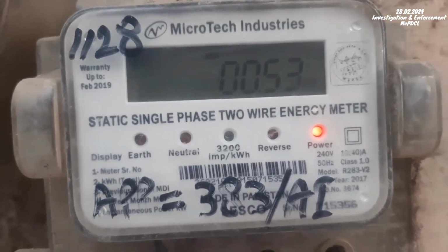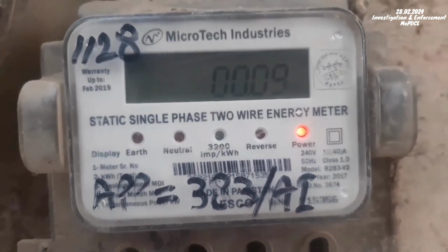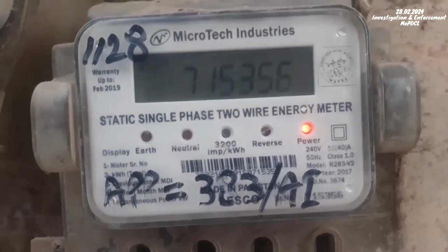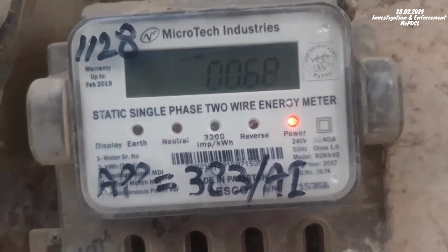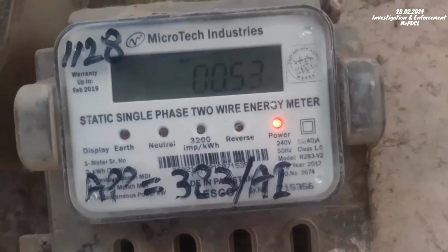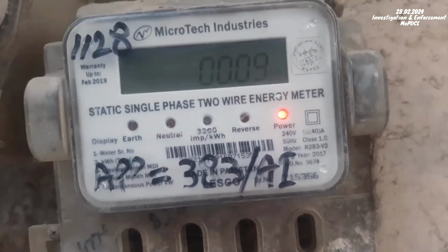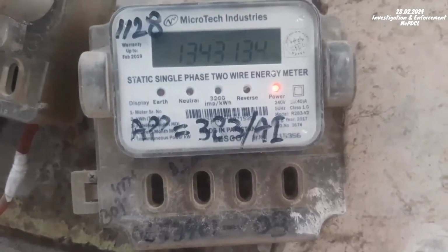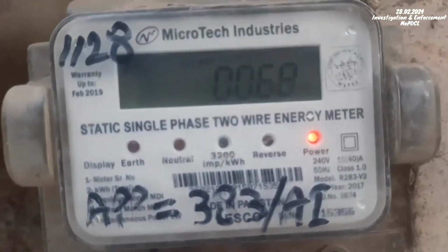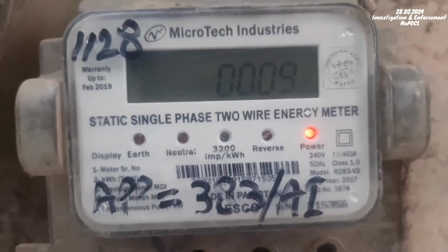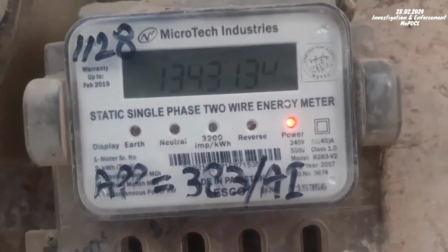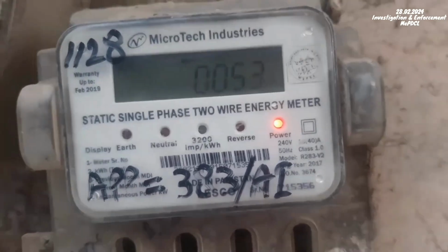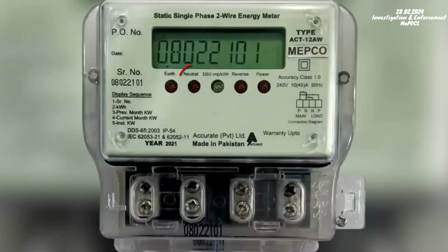It will keep blinking. It is just an impulse constant, or the meter constant, whatever term we may call it, right? So this is how it indicates your energy consumption. All right, so this is the meaning of this particular LED. It may be 1600 impulses per kilowatt hour sometimes, it may be 800, that depends on the manufacturer, right? They have different constants. This is always there, in every meter you will always have this constant. Sometimes they may give the kVARh also.